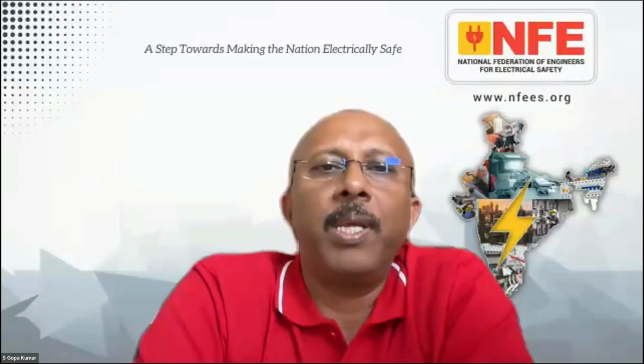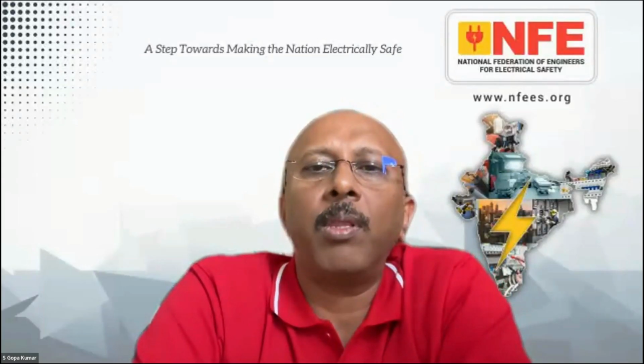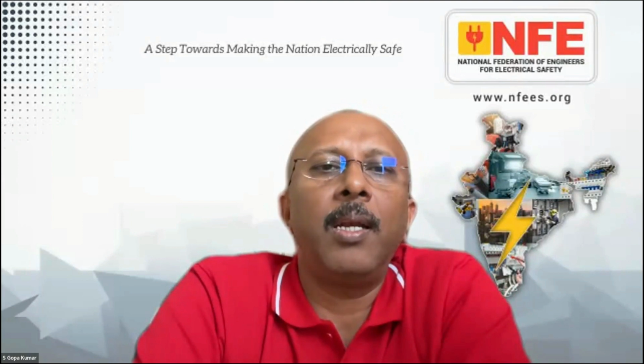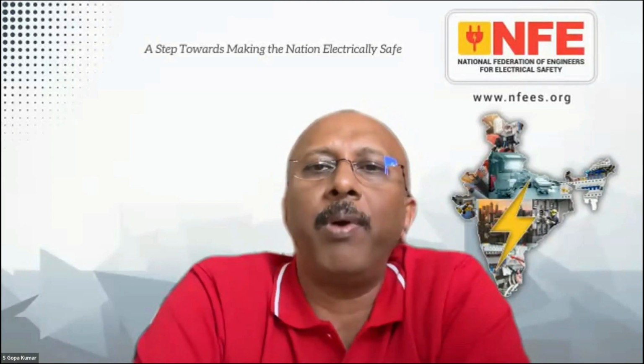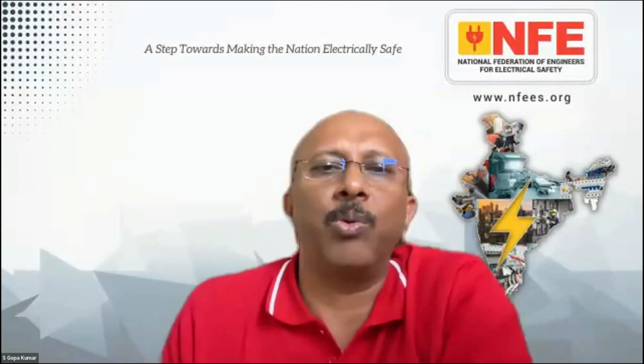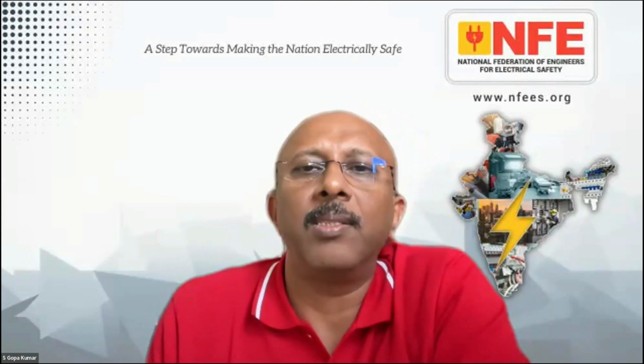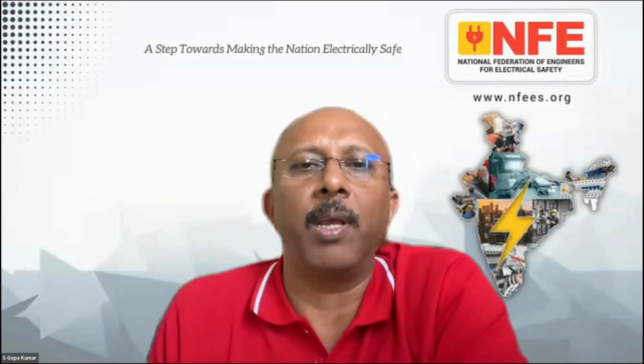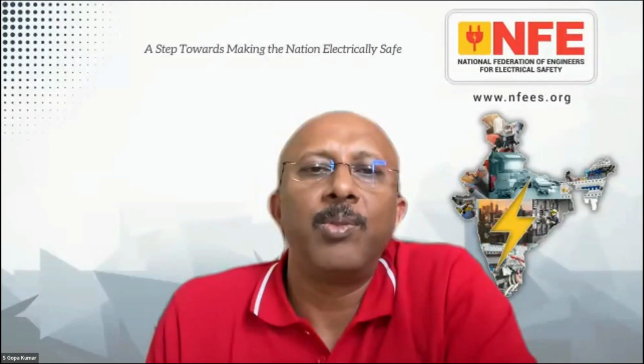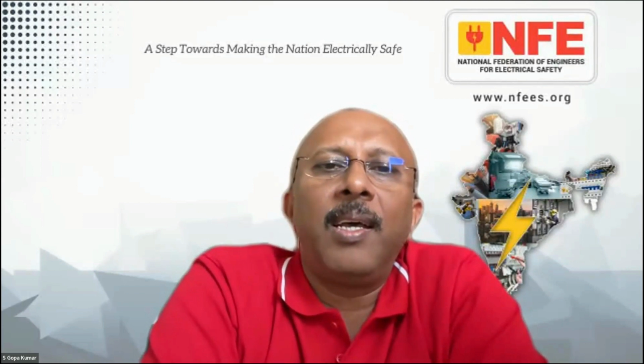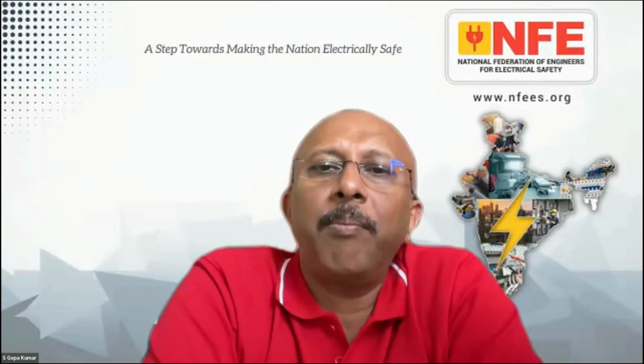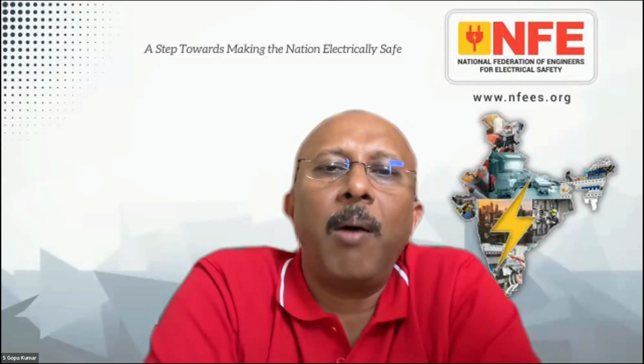The next question from Mr. Vignesh is, can I use a 1000-volt rated cable for 1200 volts if the current will be less than 0.5 amps? Of course, you cannot use it. If the cable is rated 1000 volt, then you have to use it below 1000 volt. He's saying that the current is lesser, but the point is the insulation is not rated for that value. Yes, of course.